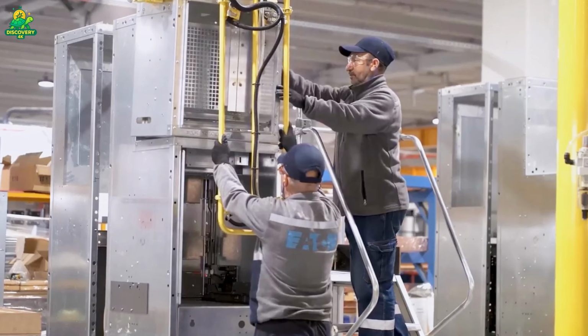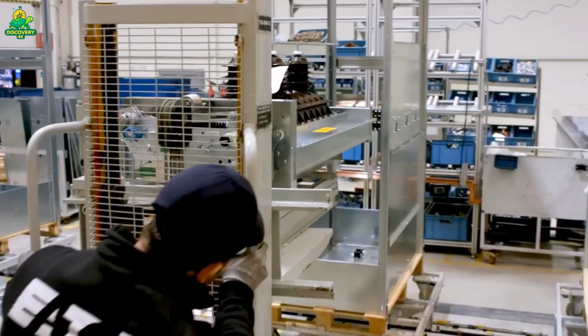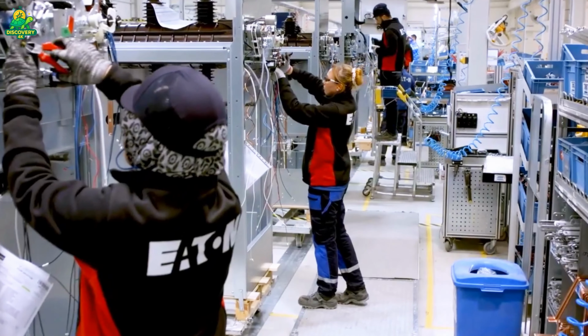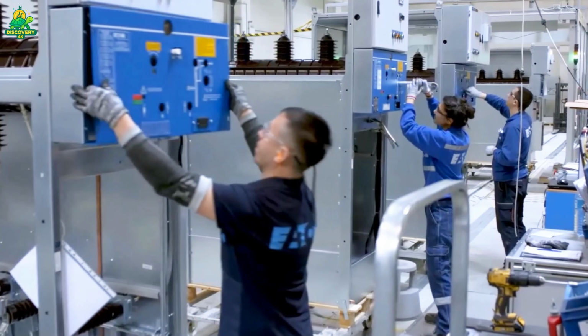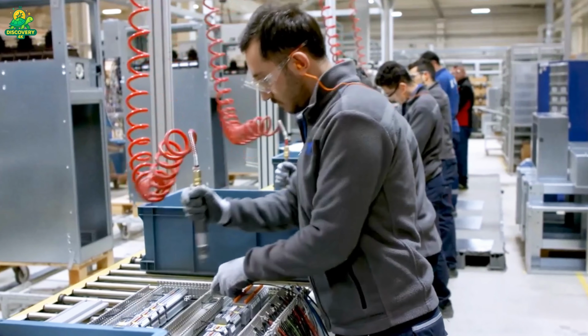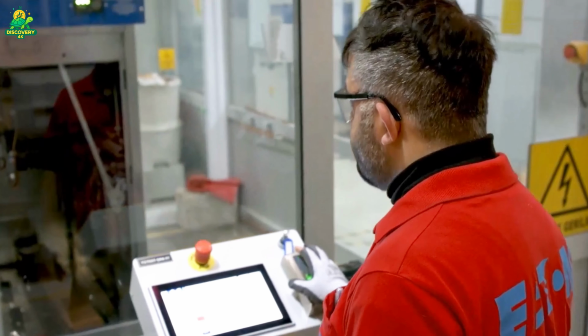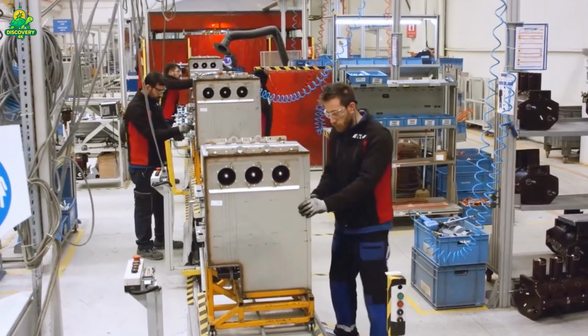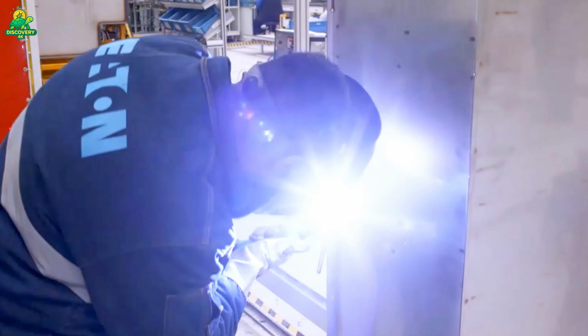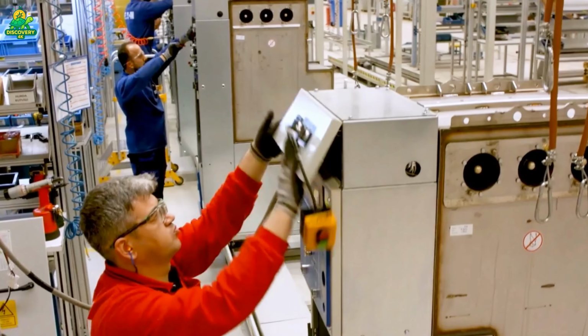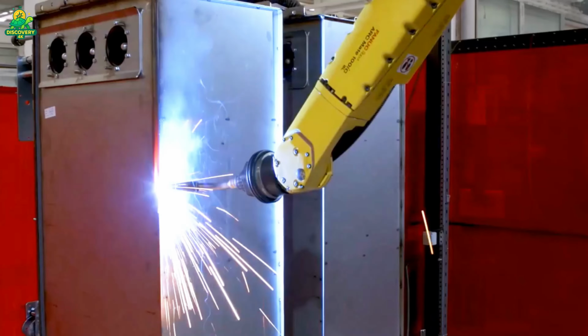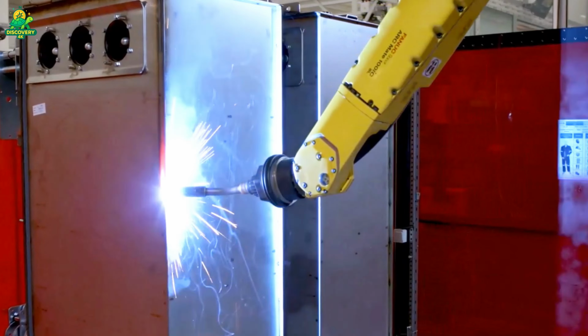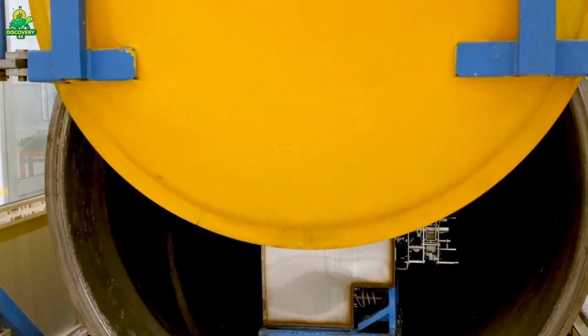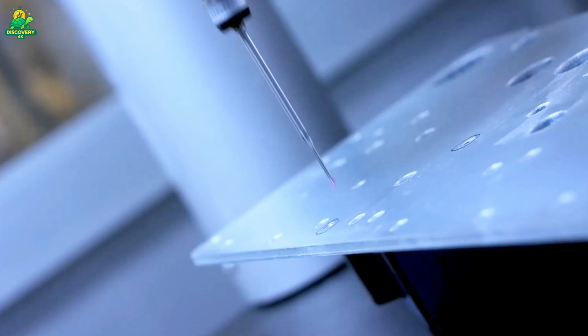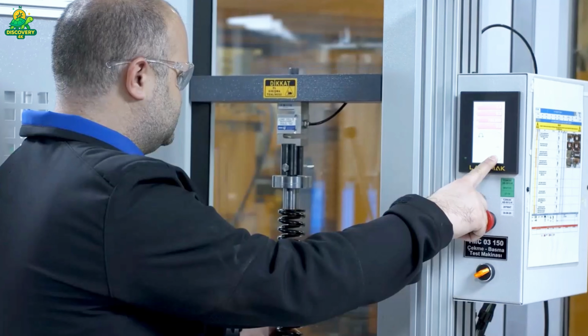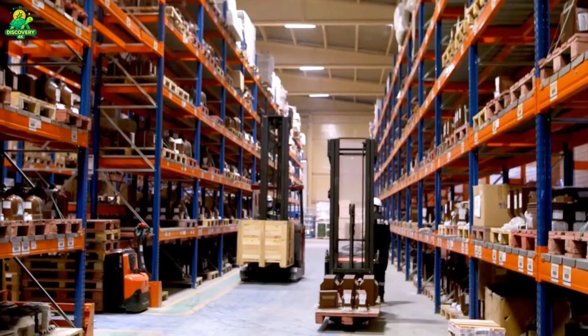Robotic arms then stack these laminations layer by layer, creating a magnetic loop, the core, where electricity will later be transformed from high voltage to low, or vice versa. The completed core can weigh up to 100 tons and is assembled using an interleaved step-lap design to minimize noise and maximize efficiency. If the core is the skeleton, then copper windings are the veins and arteries of a transformer.